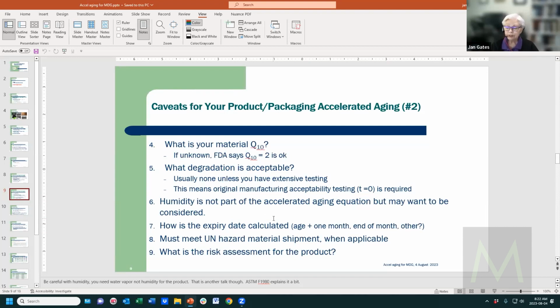Humidity is not part of accelerated aging, but you might want to consider it. But then you go into things about water vapor, and that's a whole different thing to talk about. They've got a little bit of that information in that ASTM test, so you can make sure you use the right actual humidity level. Because I have found things like 25C, if I'm having that as room temperature and I want to go to an accelerated aging of 50C or something, and the humidity at our 25C is considered 80%. But when you move it up to 50, 55C, you're only talking about a 20% humidity, because you need to worry about your water vapor, not just the relative humidity. That's a whole other talk, trying to explain that better.